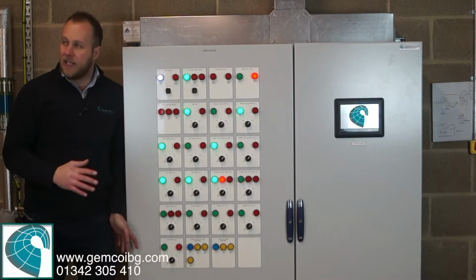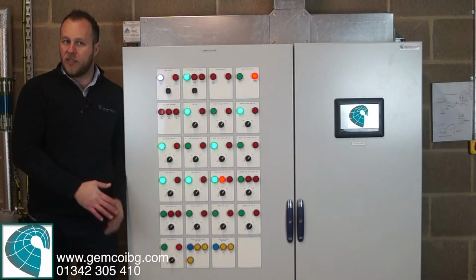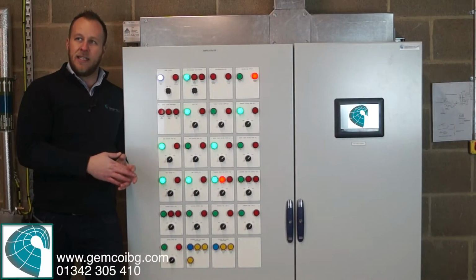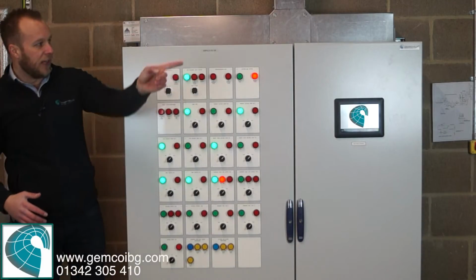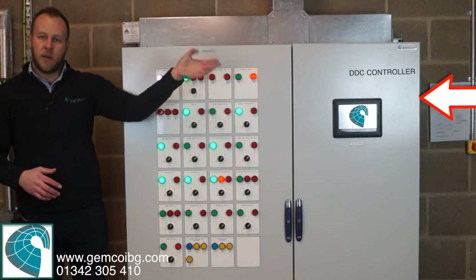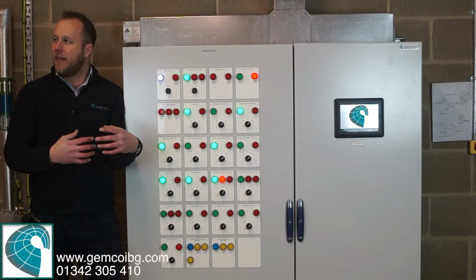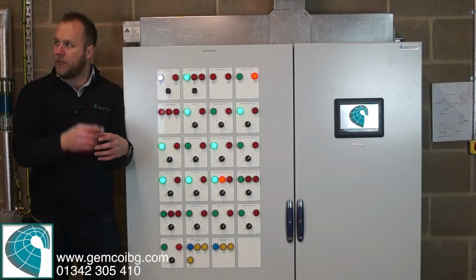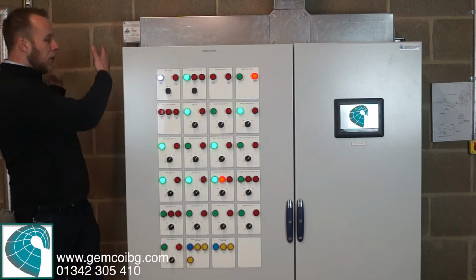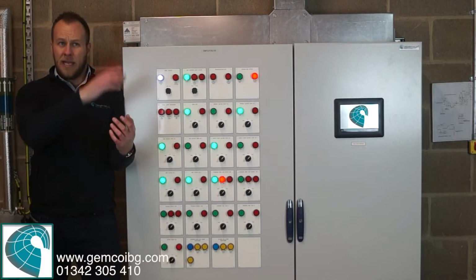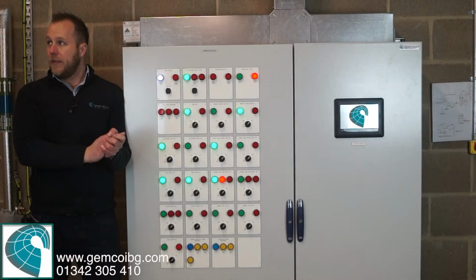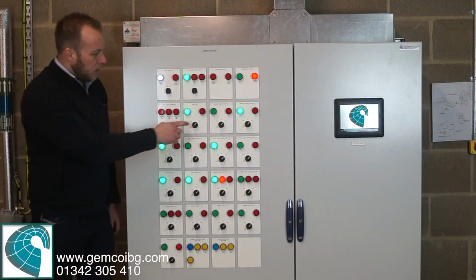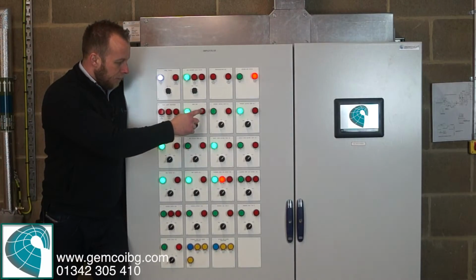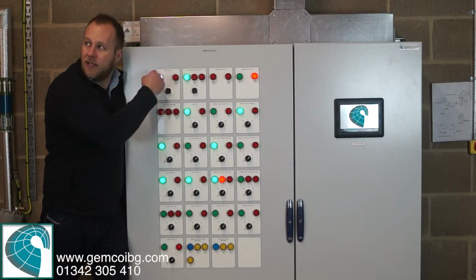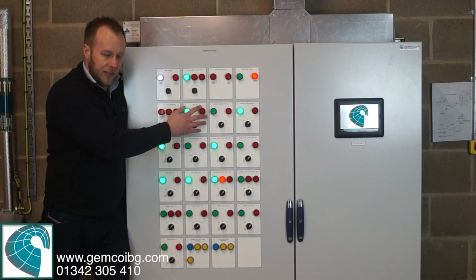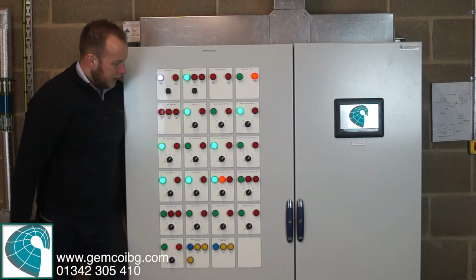The GHP is your main heat source. That is completely independent and standalone. We enable it at the start of the time zone. It starts your heating and away we go. The controller for that is on the side of the panel. Although it's part of our panel, it's not our kit. We were sent it by them just to make it look neat. They didn't want to mount it on a wall or something, so they put it on the side of our panel. But that controls your boiler. Okay. The boiler will be enabled only when these safety circuits are healthy, so they'll still be respected. They won't be able to run if there's a problem up here.